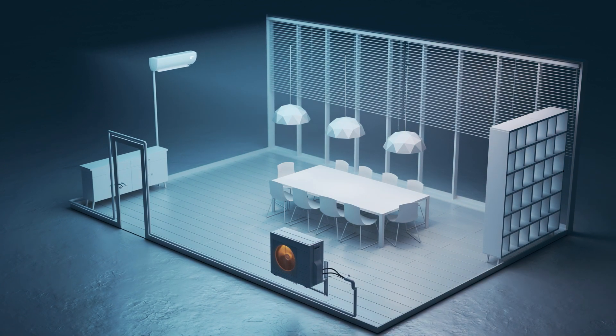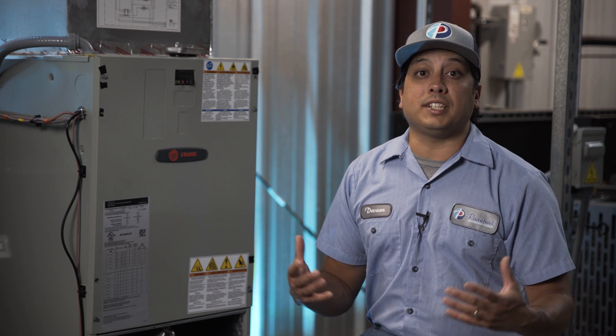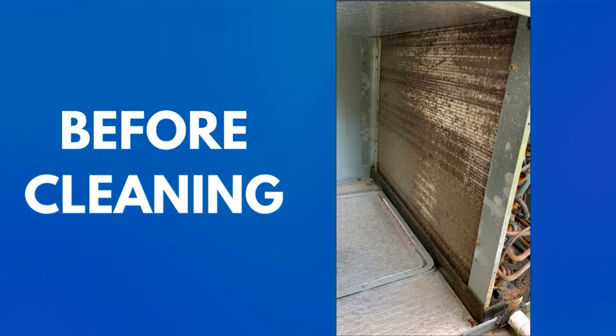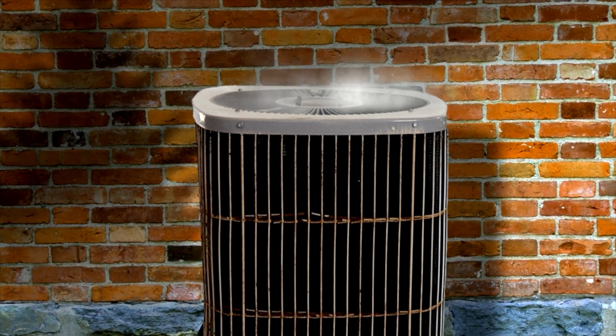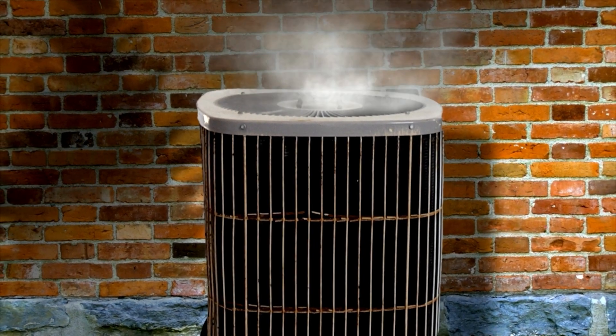The evaporator coil becomes damp during normal use due to the dehumidification process. If your evaporator coil becomes dirty, dirt, pollen, and other particles begin to stick to the evaporator coil as air passes through it. Dirty coils can use up to 40% more energy than air conditioning units with clean coils, as well as reducing the cooling function by an estimated 30% or more. Not only will your AC unit continue to lose performance and efficiency, but your monthly utility bills will continue to skyrocket if your dirty coils are left uncleaned.